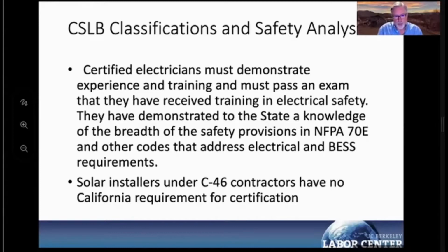Certification requires demonstrated safety competency, including methods of avoiding electrical shock hazards and arc flash, which are addressed in 70E. These methods involve performing risk assessments and protection calculations, and wearing appropriate PPE for arc flash and electrical shock, which is also referenced, for example, in the LG Resu installation manual.